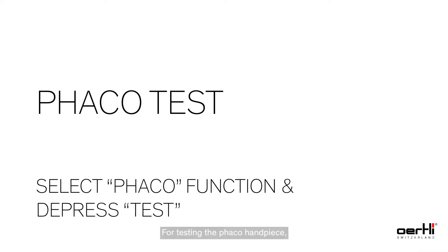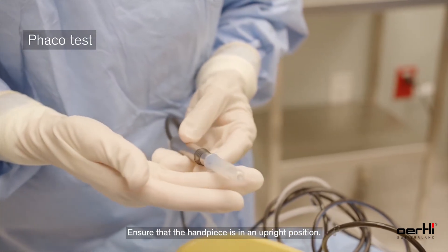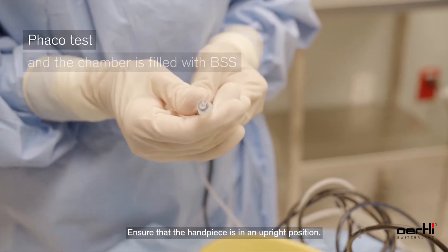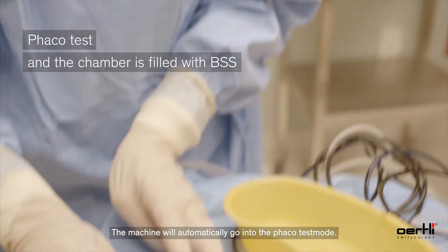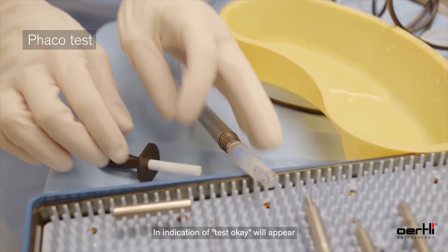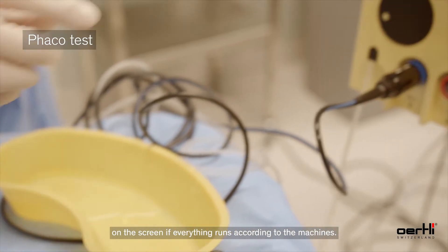For testing the Phaco handpiece, ensure the test chamber is securely on the Phaco handpiece and that the handpiece is in an upright position. The machine will automatically go into the Phaco test mode. An indication of 'test okay' will appear on the screen if everything runs according to the machine's parameters.